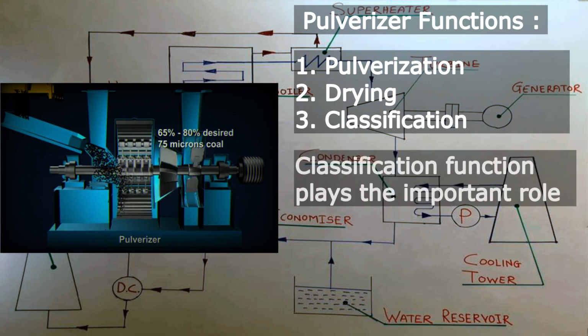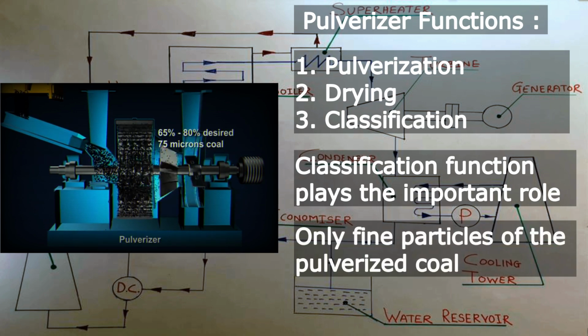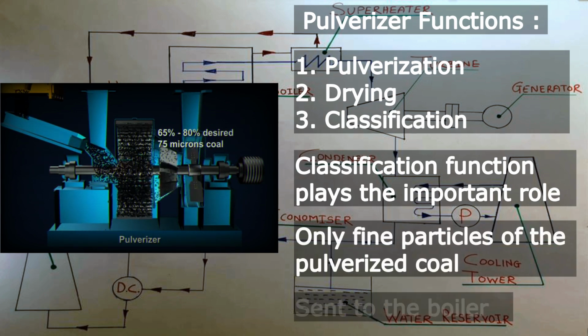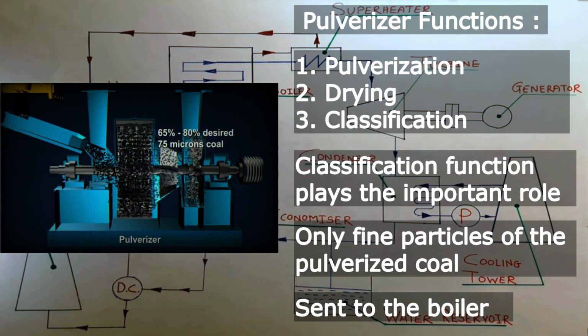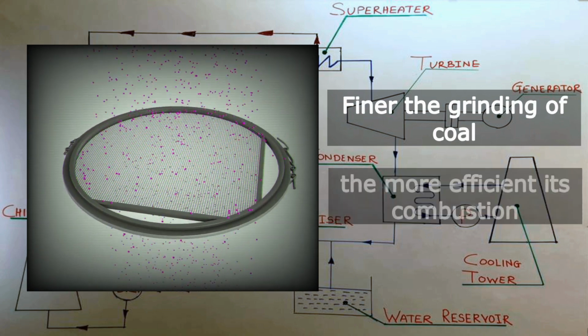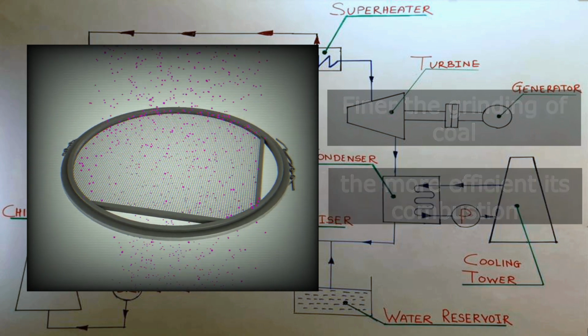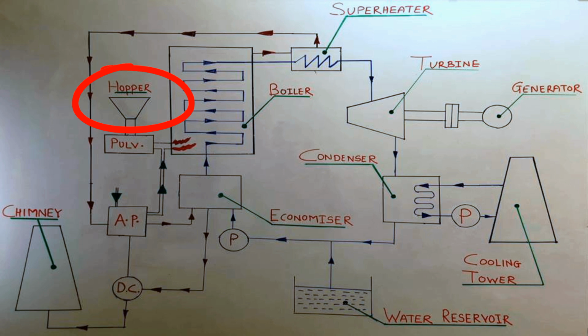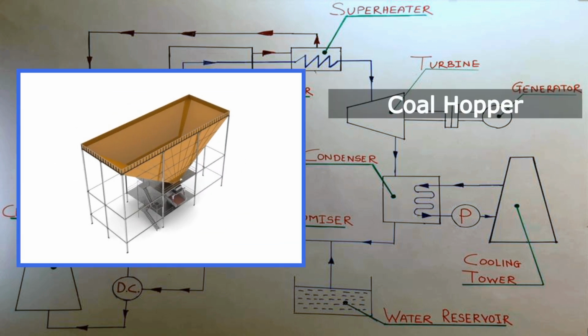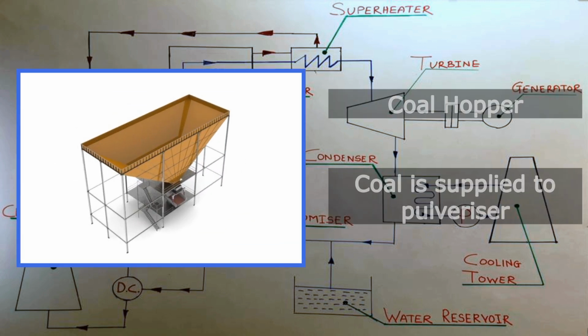Out of these three functions, the classification function plays the important role of ensuring that only fine particles of the pulverized coal are sent to the furnace, that is combustion chamber of the boiler. Because finer the grinding of coal, the more efficient its combustion. One more element you can see here, that is a hopper. It is a coal hopper through which the coal is fed into the pulverizer.